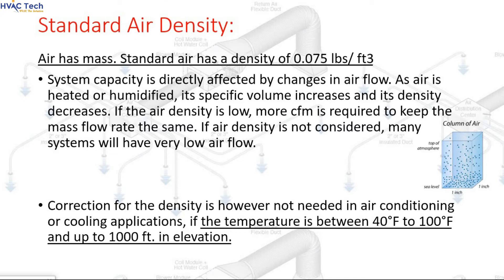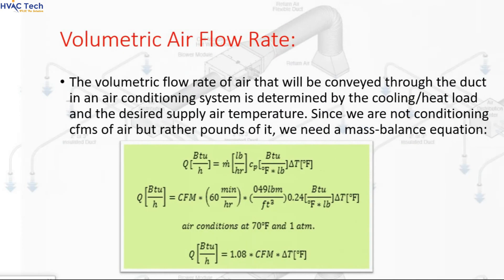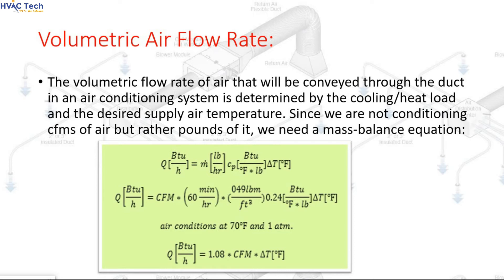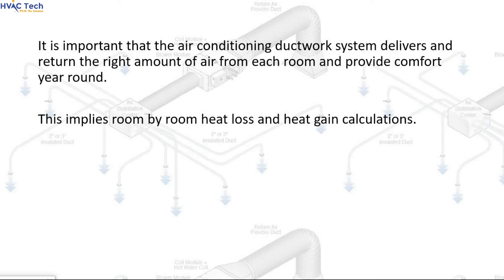Correction for density is not needed in air conditioning or cooling applications if the temperature is between 40°F and 100°F and up to 1,000 feet in elevation. The volumetric flow rate of air conveyed through the duct in an air conditioning system is determined by the cooling/heat load and the desired supply air temperature. Since we are not conditioning CFMs of air but rather pounds of it, we need a mass balance equation. It is important that the ductwork system delivers and returns the right amount of air from each room to provide comfort year-round, implying room-by-room heat loss and heat gain calculations.